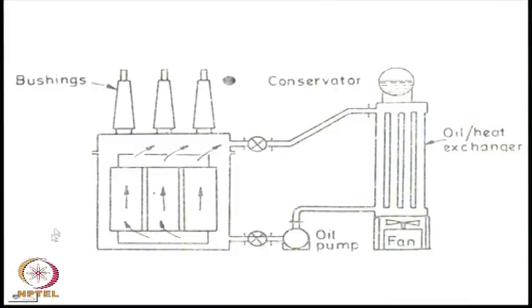This figure shows such an arrangement. These are the transformer core and winding. This is placed inside a steel tank and the tank is filled with transformer oil. The reason for using oil is that it is a better conductor of heat than air and it has a higher coefficient of volume expansion with temperature. Therefore, sufficient circulation is easily obtained on account of the natural thermal head that occurs in the transformer because of heat produced by different mechanisms of loss such as the core loss and the copper loss.